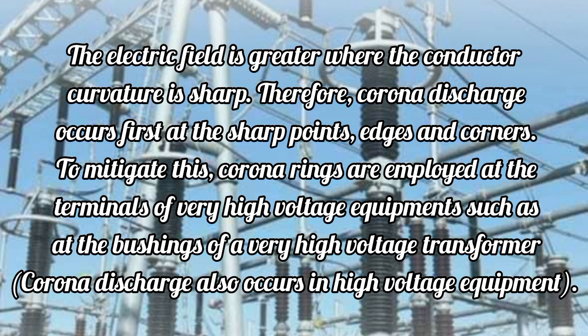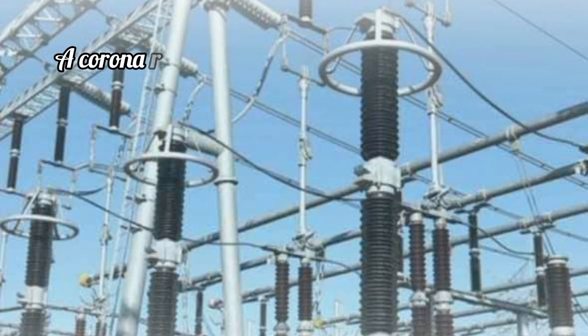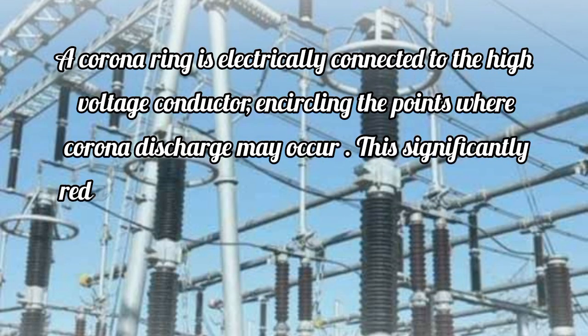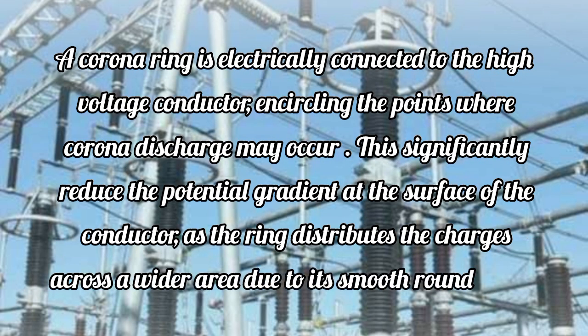To mitigate this, corona rings are employed at the terminals of very high voltage equipment, such as at the bushings of a very high voltage transformer. Corona discharge also occurs in high voltage equipment. A corona ring is electrically connected to the high voltage conductor, encircling the points where corona discharge may occur. This significantly reduces the potential gradient at the surface of the conductor, as the ring distributes the charges across a wider area due to its smooth round shape.